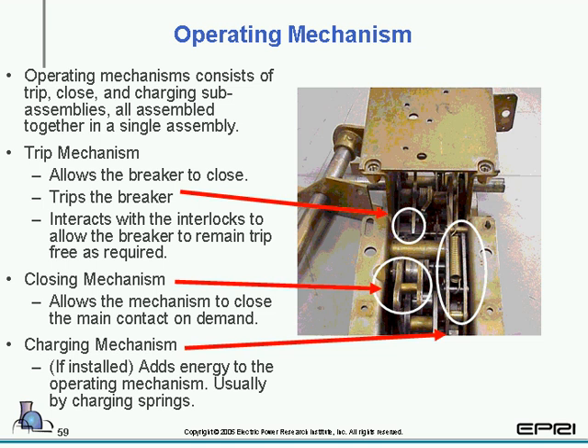All operating mechanisms can still be broken down into their sub-assemblies. Three of the most common are the trip mechanism. Now, the trip mechanism must be closed to allow the breaker to be closed. If it is not, the trip breaker can interact with interlocks, which allow the breaker to remain trip-free. The closing mechanism, which allows the moving contacts to actually go from the open state to the closed state, and then a charging mechanism if it is installed. And the thing to keep in mind is, even though it's an integral part of one unit, they can all be broken down into separate subsections, or that mechanism could be subdivided and looked at separately.